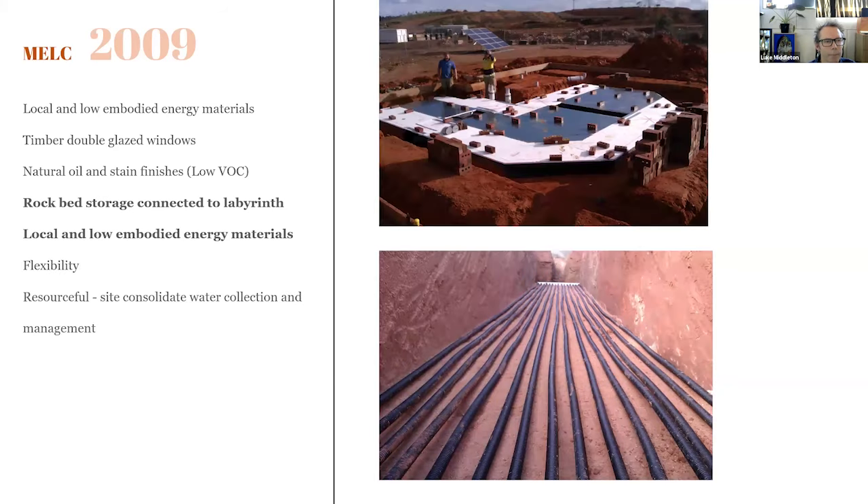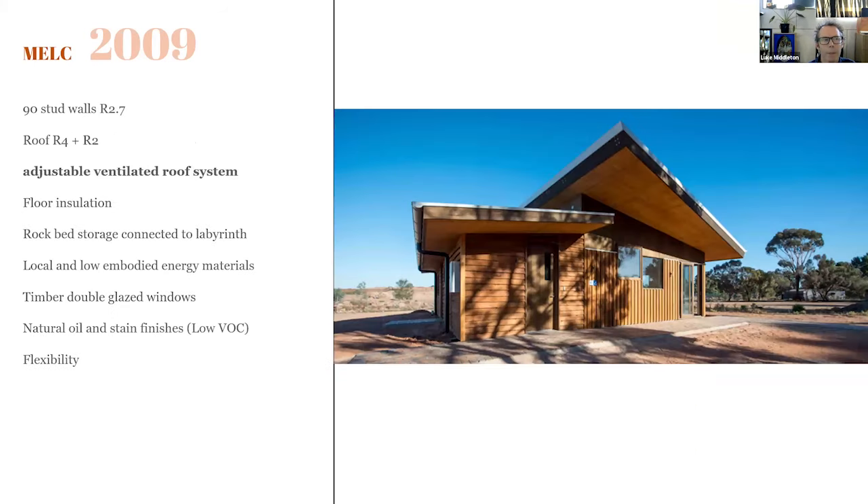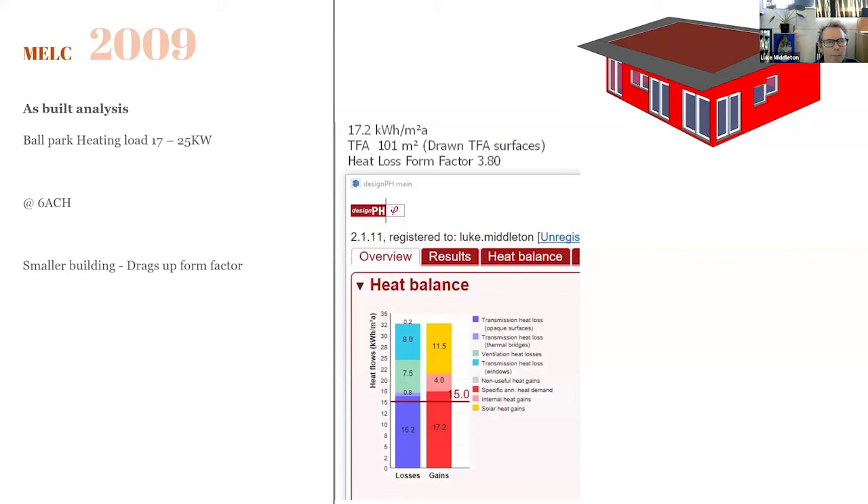We suggested adding some low-tech energy management systems to take advantage of the semi-arid climate. We introduced a rock bed plenum to enhance energy storage that captures cool air during summer nights and feeds an underground air labyrinth. In winter it does a reverse — the excess heat is fed into the rock bed and maintains warmth on cold and cloudy days. We've done the modelling and this building had some issues. We did have an adaptable skillion roof that consolidated three zones of insulation in winter and became a vented parasol roof in summer.